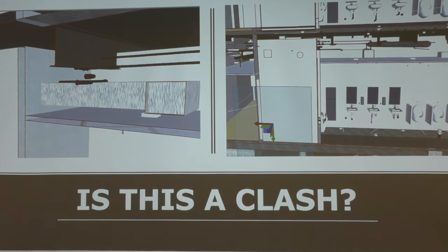And he wouldn't have a section through there, but just because we're working in a 3D drawing, he's got a section there, but look how big the ceiling void is. The ceiling void's like 600 mil underneath it. So if you can't fit that in, and you're going to install it in front of the pipe or through the beam, you're going to be a bit silly. I would call it a resolvable clash, rather than saying it's not a clash. But it is a clash, unless it's resolved.